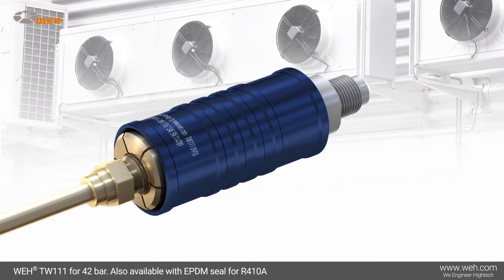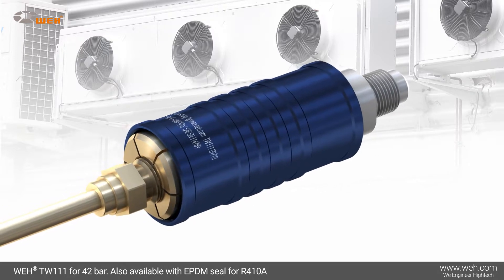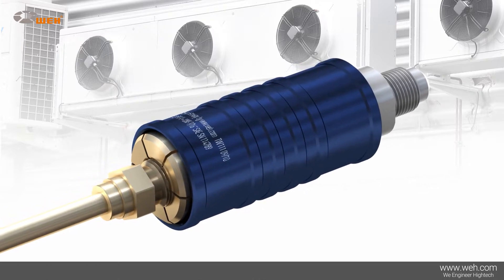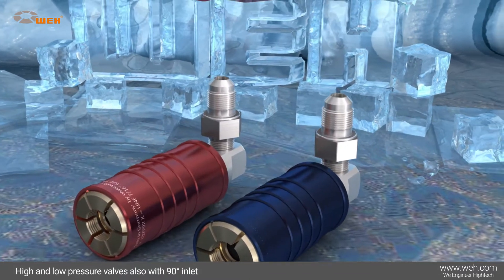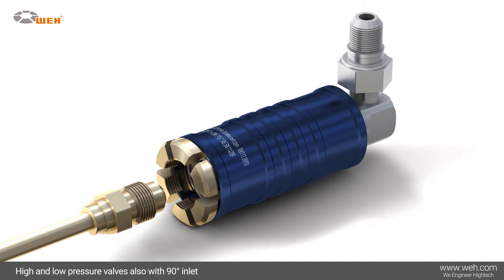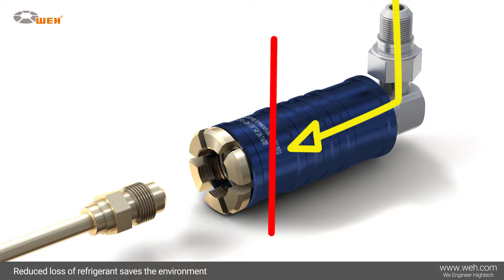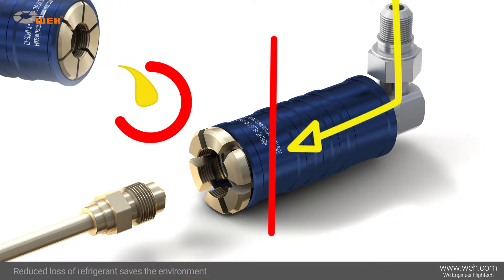The connector is equipped with a chloroprene front seal as standard. For filling of refrigerant R410A, an EPDM front seal is used. Both versions are available with either inline or 90-degree media inlets. When filling is completed, an integrated shut-off valve prevents the escape of refrigerant, which remains in the filling hose awaiting correct disposal.